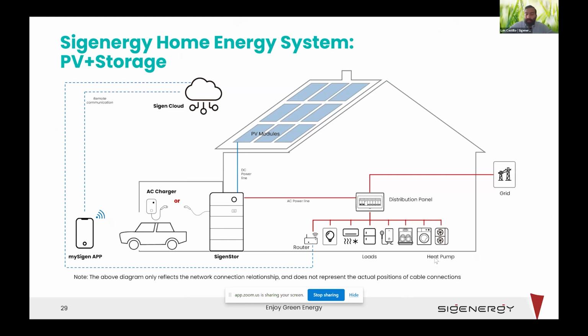You will have an AC line connected to your distribution panel, and a power sensor hardwired through RS-485 to the energy controller. That's your electrical installation. The rest will be your connectivity, which you could hardwire to the router, connect to Wi-Fi through the built-in Wi-Fi module on the unit using the antenna that comes in the box, or connect to 4G. You can use one, or all three. The more connectivity in your system, the more robust it will be. We recommend at least two methods of communication, so you have a backup.